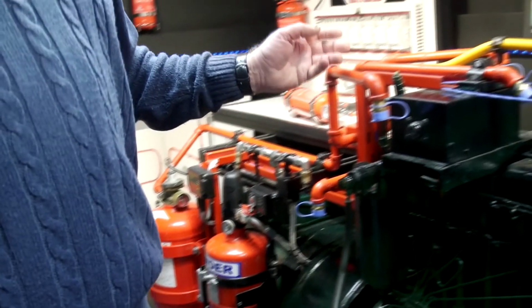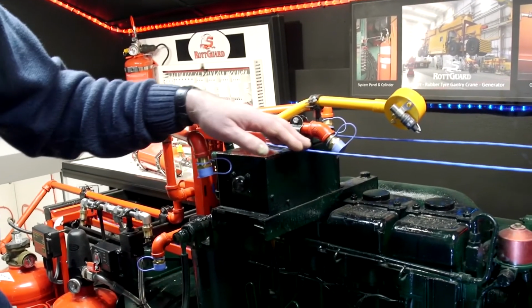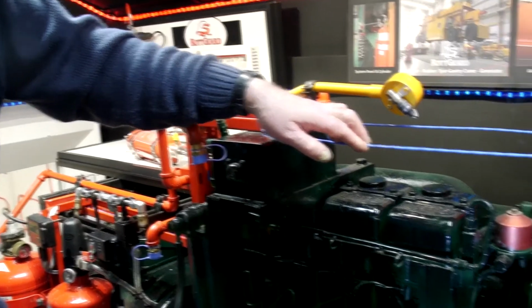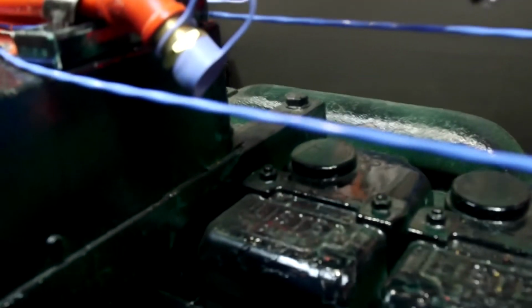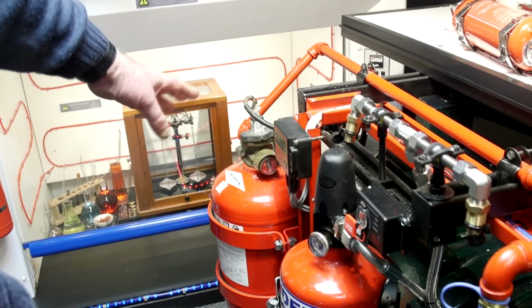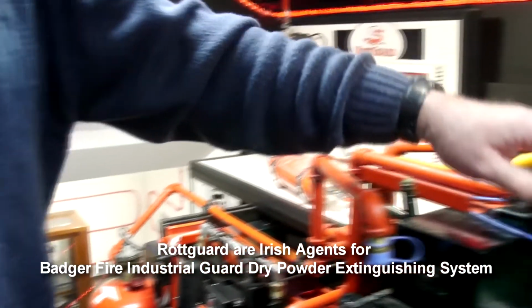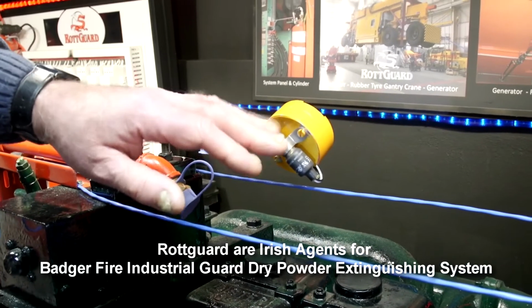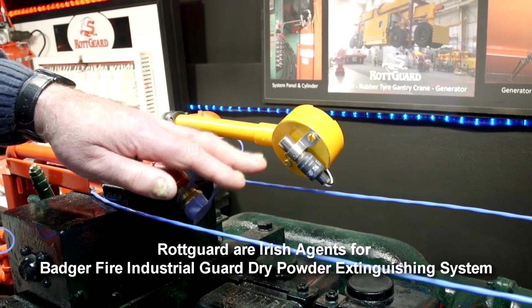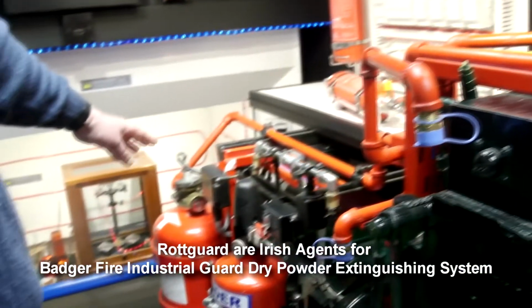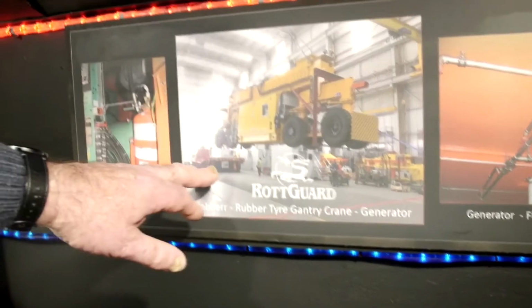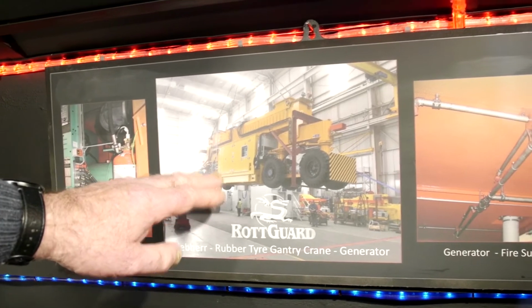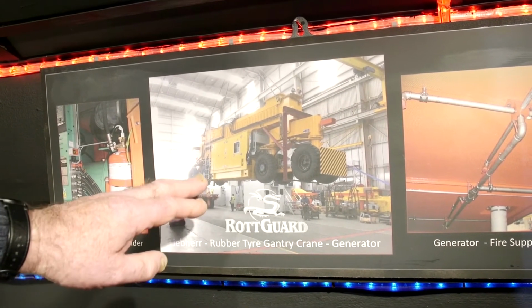They can be activated manually or they can be activated automatically by means of this linear heat detection cable, which will trigger an alarm on the control panel. This larger cylinder here, which is a 25-pound cylinder, could be triggered by this point heat detector, which come at different temperature settings. There are examples here of systems that we installed for Liebherr in the images behind us. This one here is a generator enclosure on one of their rubber tire gantry cranes.